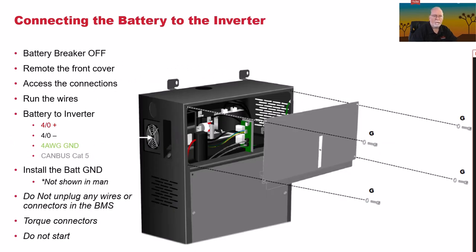Connecting the battery to the inverter, of course, you want to make sure the battery breaker is off. You want to make sure the inverter is off and that all sources have been terminated at their source of origination. Just make sure that you lock out, tag out the main panel so that you don't have AC running through it. So when you go to connect it, you're going to remove this top panel.